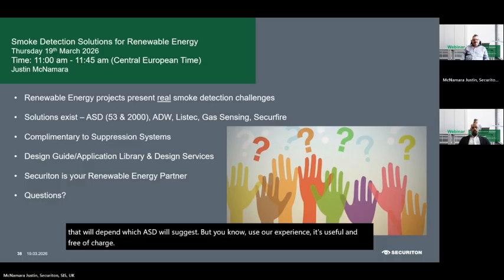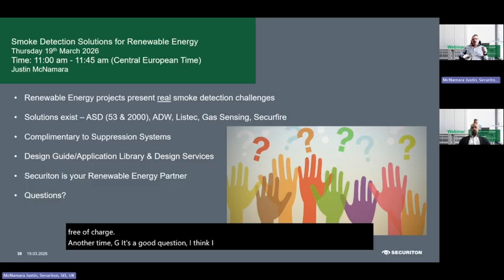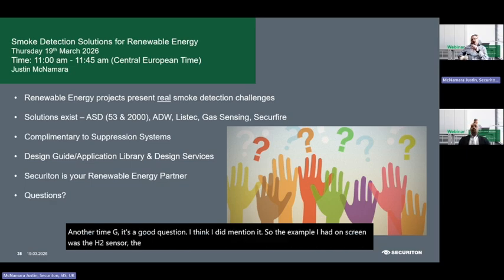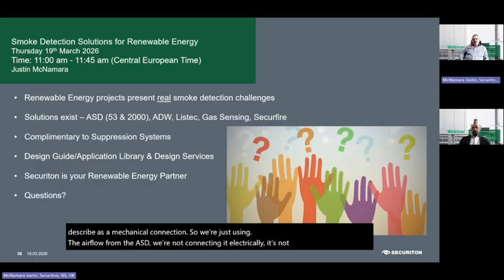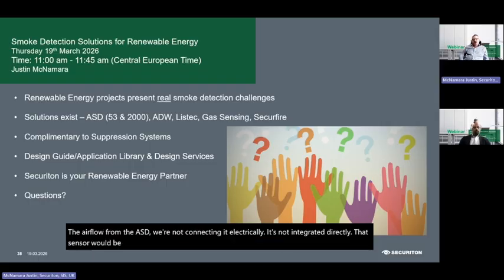The next question: do your gas sensors integrate directly with your ASD? No, they don't, good question. The example I had on screen was the H2 sensor, the flammable sensor, using the exhaust on an ASD, but I'd describe that as a mechanical connection - we're just using the airflow from the ASD. We're not connecting it electrically. That sensor would be integrated into a fire panel or a building management system or something else, not connected electrically to the ASD.